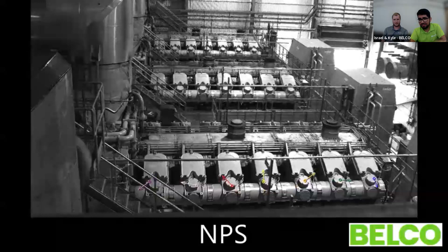I'll start off. This is looking at a jacket cooling pump motor set failure that we identified. We used the motion amplification camera for this one. It started off where we were doing vibration readings on the motor inboard bearings. We were frequently finding them quite high. We were having multiple coupling failures with this motor. It added up to be about $12,000 of cost over 2 years.